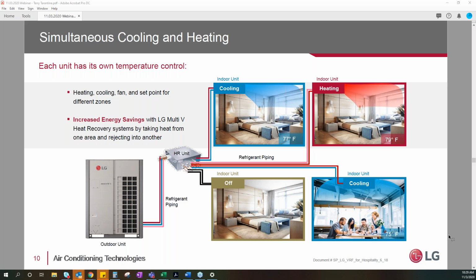And again, simultaneous heating and cooling. Water source and VRF do a great job of pulling heat from one space and transferring it to another. So again, this is that scenario we talked about where one side of the building may be in sunlight and needs cooling. Another spot is not in the sunlight and needs heating. We can just transfer those BTUs around from one spot to another.